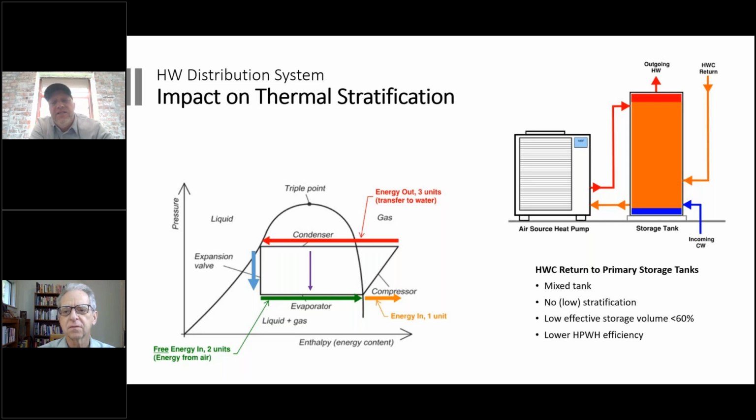And that's sort of a reason to decouple them, because everything's happening pretty fast, so you want to be careful that if the heat pump goes out and your hot water circ comes in, it'll wipe out all your storage. But that's really, I think, from a distribution standpoint, the reason to keep that temperature maintenance system isolated from your gold, your hot water that's primed and ready to go.